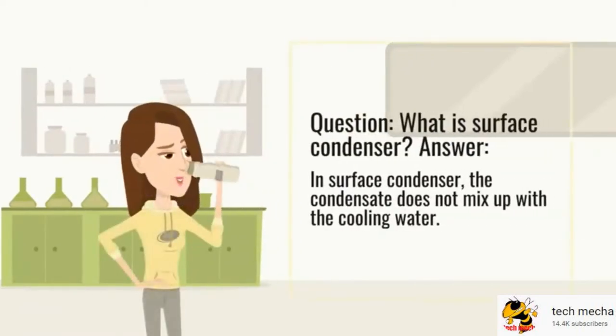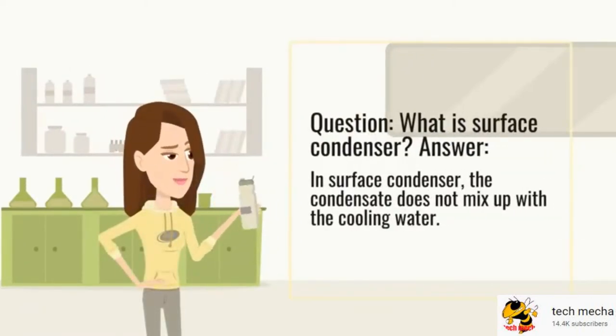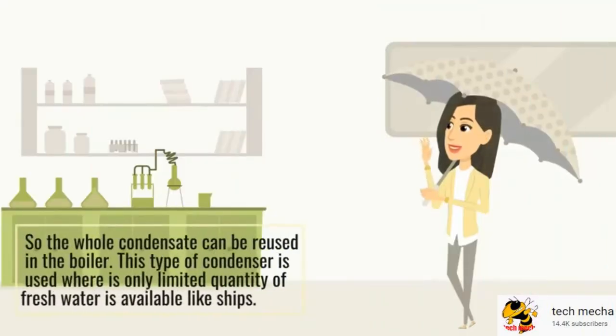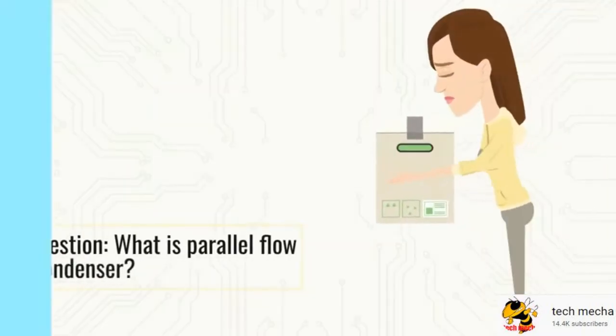What is a surface condenser? In a surface condenser, the condensate does not mix up with the cooling water, so the whole condensate can be reused in the boiler. This type of condenser is used where only a limited quantity of fresh water is available, such as on ships.